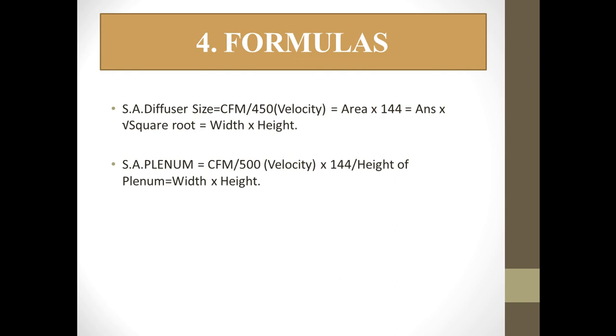Supply air plenum is used to connect two ducts or connect flexible ducts in HVAC ducting design. To calculate supply air plenum size: Supply Air Plenum = CFM / 500, where 500 is the standard velocity. Multiply the result by 144, then divide by the plenum height to get the width. This gives you the width, height, and length of the plenum. Thank you for watching my channel.